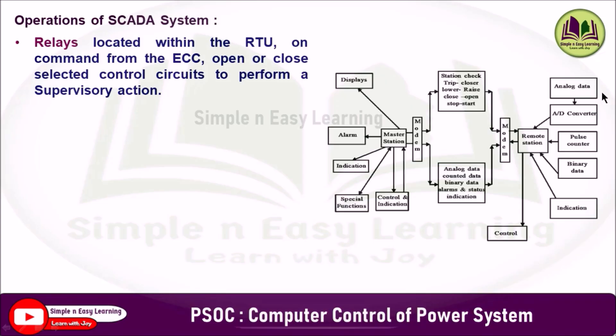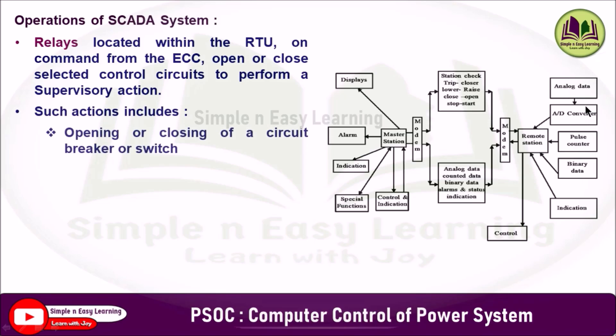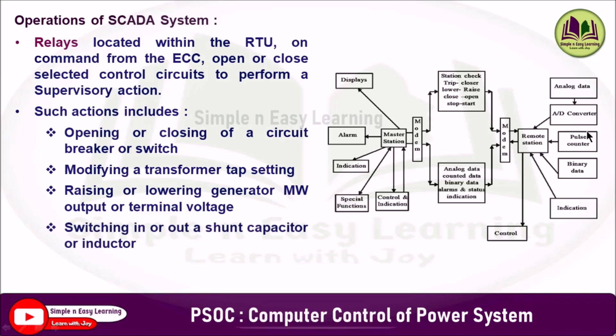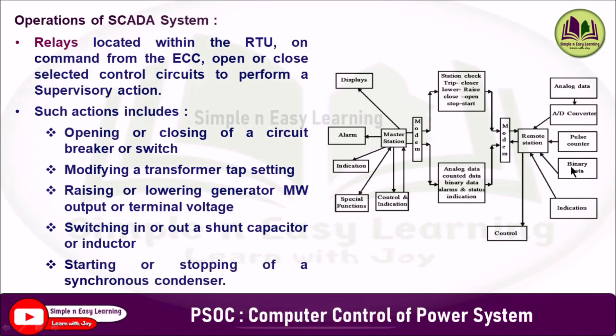The relays located within the RTU, on command received from the ECC, open or close the selected control circuit to perform a supervisory action. Such actions include opening or closing of a circuit breaker or switch, modifying the transformer tap setting, raising or lowering generator megawatt output or terminal voltage, switching in or out a shunt capacitor or inductor for voltage control, and starting or stopping of a synchronous condenser.